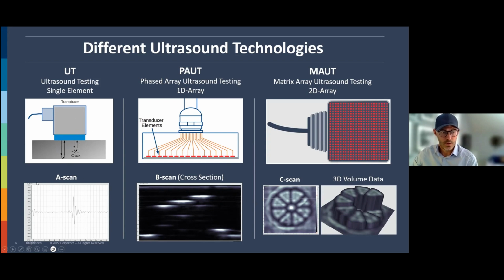So that results in what we call an A scan. You get a small echo here, a penetration echo in the beginning, and then here you see a larger echo in the back wall. This is the pulse of that acoustic wave that you sent out. If you hit the back wall here, then maybe your A scan is located here. But if you hit the crack, then the A scan comes earlier. And then you can see that you have some sort of object that is preventing the sound to travel through your medium. And that's what you use to inspect. For example, to inspect on an aircraft, you need 3,000 hours of training to be able to use this kind of technology. It's kind of old technology. It's still very much used today, but it requires more expertise to use it.